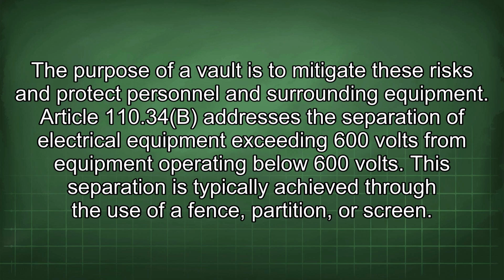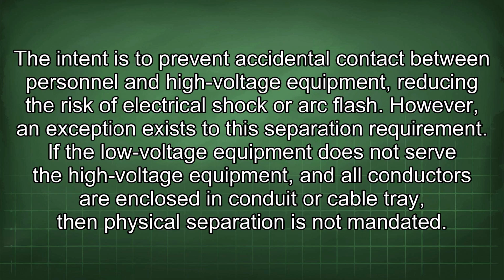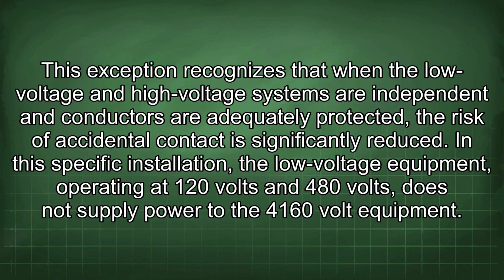Article 110.34b addresses the separation of electrical equipment exceeding 600 volts from equipment operating below 600 volts. This separation is typically achieved through the use of a fence, partition, or screen. The intent is to prevent accidental contact between personnel and high-voltage equipment, reducing the risk of electrical shock or arc flash. However, an exception exists to the separation requirement. If the low-voltage equipment does not serve the high-voltage equipment and all conductors are enclosed in conduit or cable tray, then physical separation is not mandated. This exception recognizes that when the low-voltage and high-voltage systems are independent and conductors are adequately protected, the risk of accidental contact is significantly reduced.